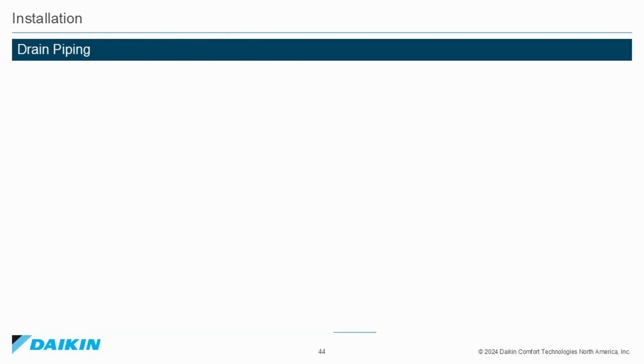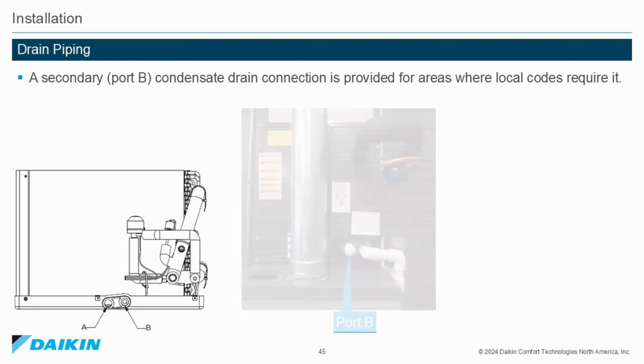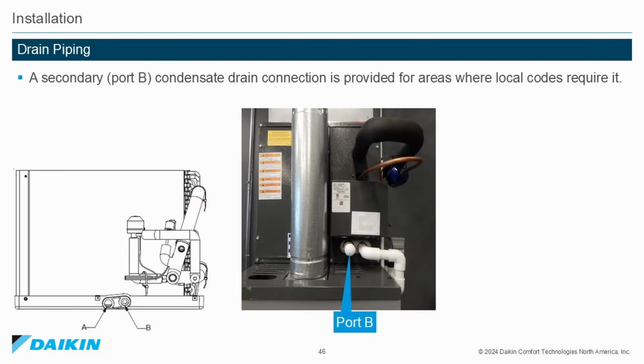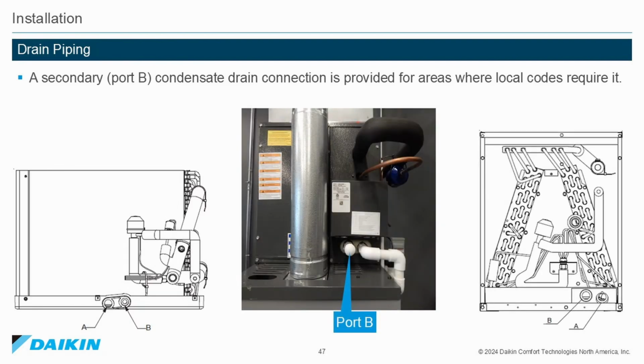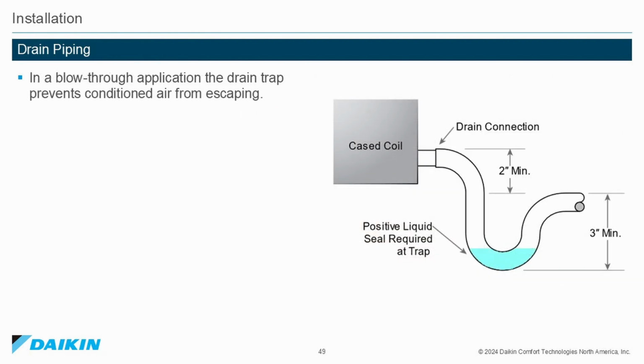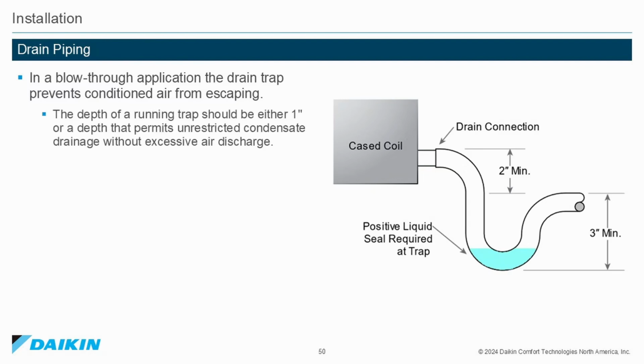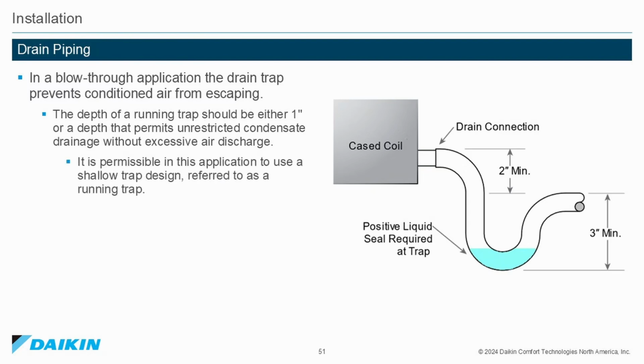Drain piping. A secondary Port B condensate drain connection is provided for areas where local codes require it. In a blow-through application, the drain trap prevents conditioned air from escaping. The depth of a running trap should be either 1 inch or a depth that permits unrestricted condensate drainage without excessive air discharge. It is permissible in this application to use a shallow trap design, referred to as a running trap.